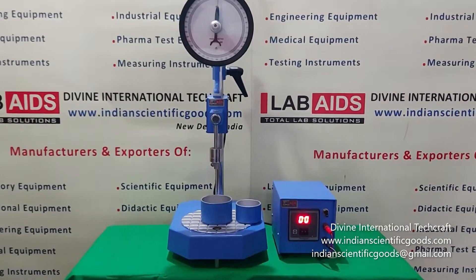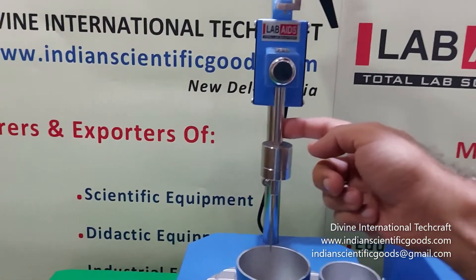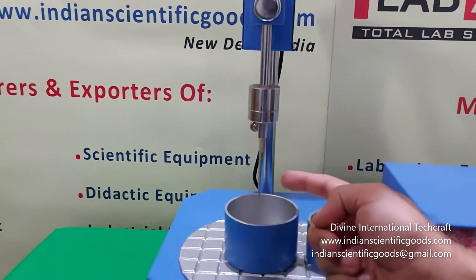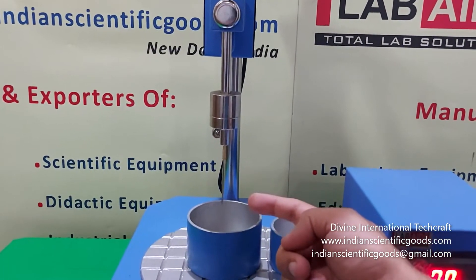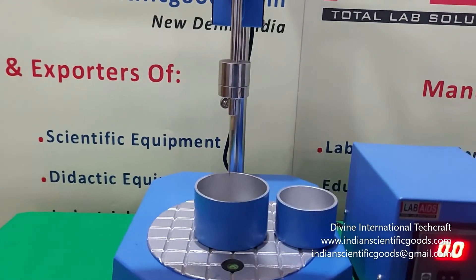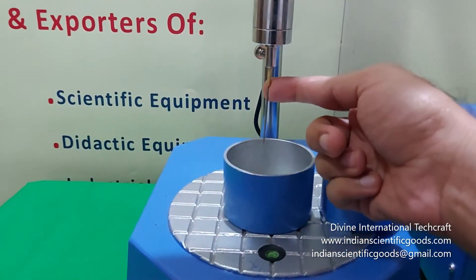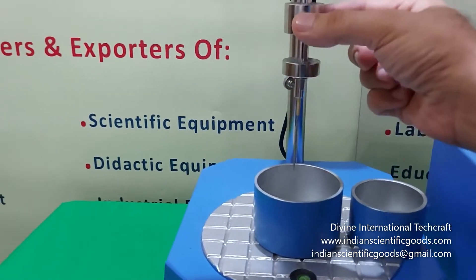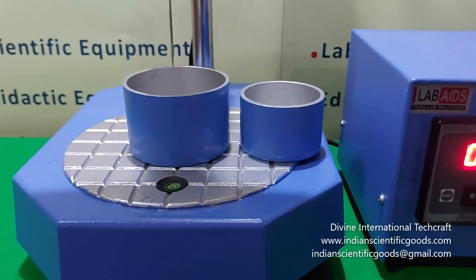The penetrometer is supplied with a plunger whose weight is 47.5 grams. Any needle or cone with a standard 1/8-inch, that is 3 mm diameter stem, may be mounted to the plunger assembly. It is supplied with a standard 2.5 gram ASTM D5 needle and two additional loading weights of 50 grams and 100 grams. Two penetration containers are provided.